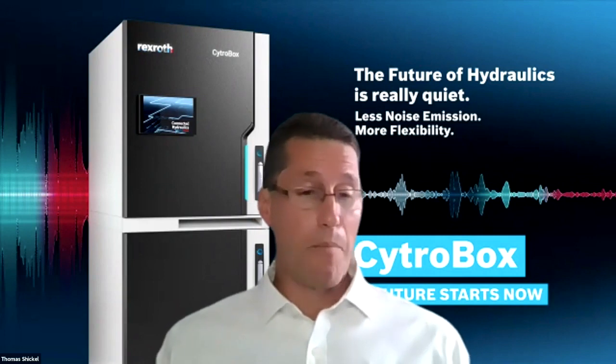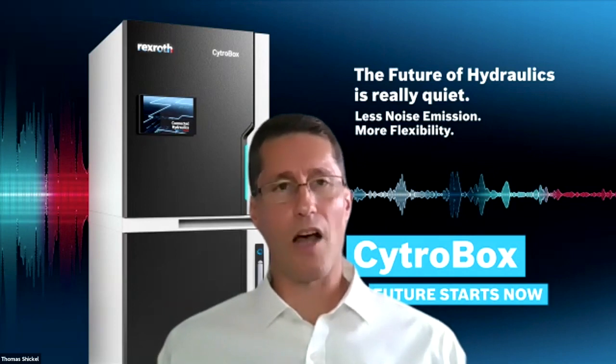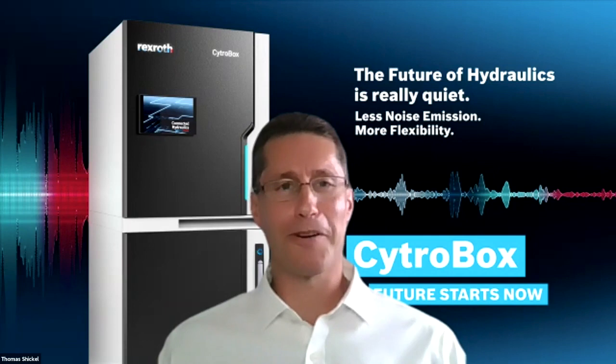So I would say do frequent sampling, but you really have to get to the problem of what is the cause. Is the preservative package falling out? Do you have a hot spot in your system? And so again, it's just trending. Make sure you're changing out your filters and keeping an eye on the health of the fluid. As you come back and you're seeing that it's healthy after checking on a weekly basis, you can go to a monthly basis and so on. But depending on what you're experiencing is going to be depending on what your solution needs to be.